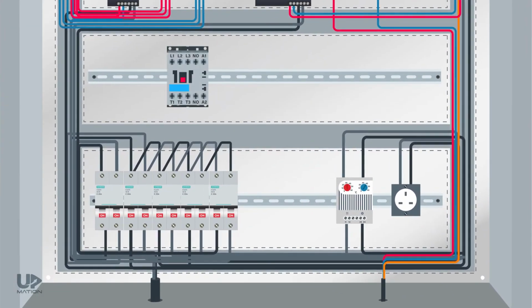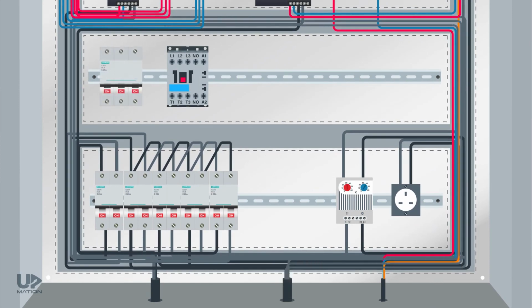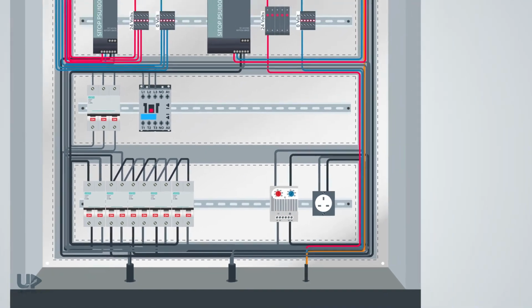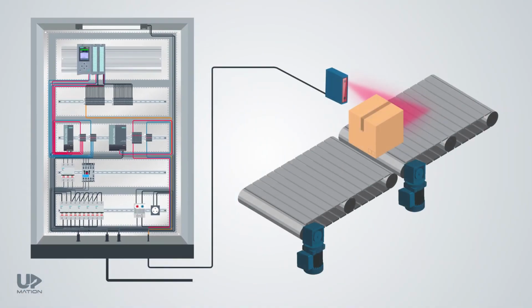To do so, we should add a contactor to our control panel. Connect a three-phase power to its input and lay a cable between the contactor and the motor connection box. Actually, when we have three-phase power within our electrical control panel, the arrangement of the panel would be somehow different from what you see here. But let's take it easy and move on for now. As soon as the PLC output card energizes the contactor, it will transfer the three-phase power to the electric motor. You'll also find some relays in the control panel to command the single-phase actuators and control devices at site like solenoid valves. As you'll see in future videos, the electrical panels and devices are scattered throughout the whole plant, and they should be interconnected to each other despite the different communication protocols they might use.